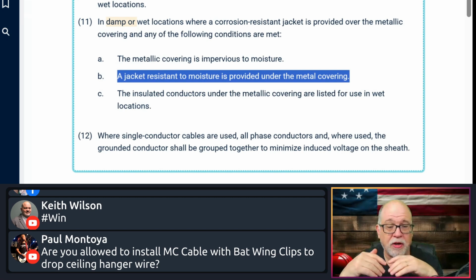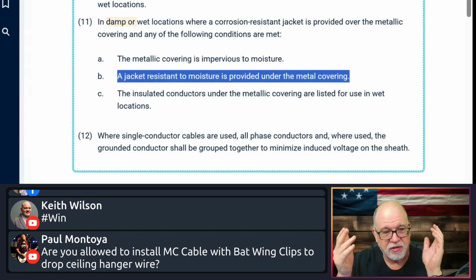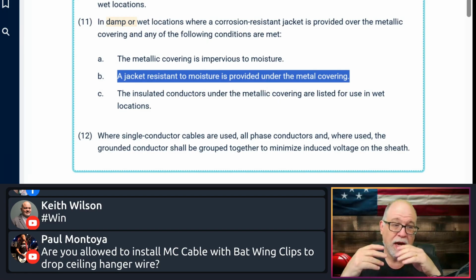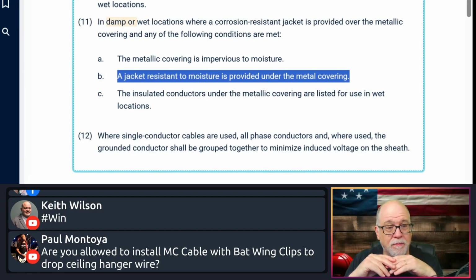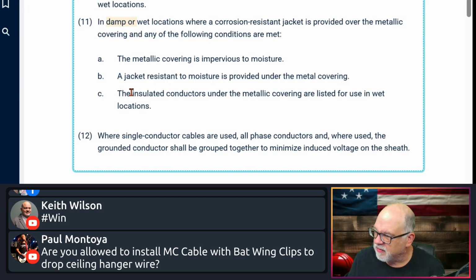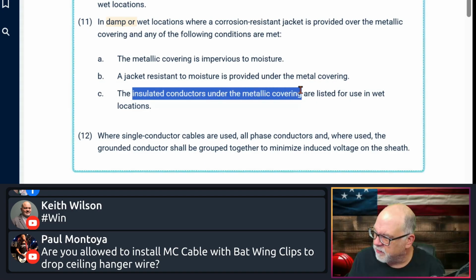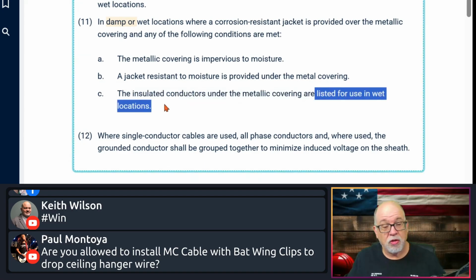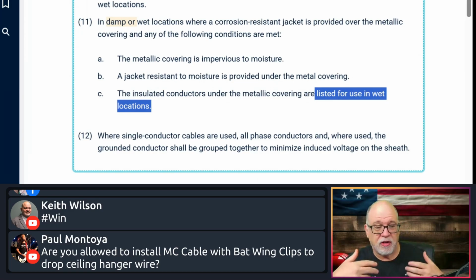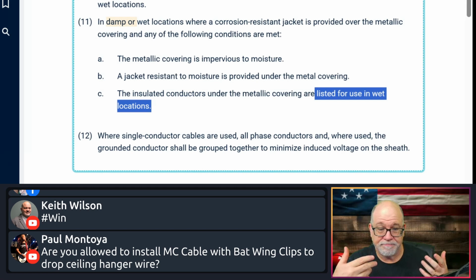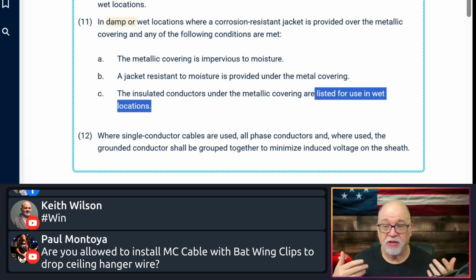Most of the stuff that we put around our conductors inside of an MC, the binding, whether it's paper or polymeric, is not resistant to moisture. So how do we get around that? Well, we get around that with the third option here. We see the insulated conductors under the metallic covering are listed for use in wet locations. So this is why you see a PVC jacketed MC product, and the conductors inside of it are wet location rated. Because it's wet location rated and it has that impervious covering on it, now it can be used in a damp and a wet location.